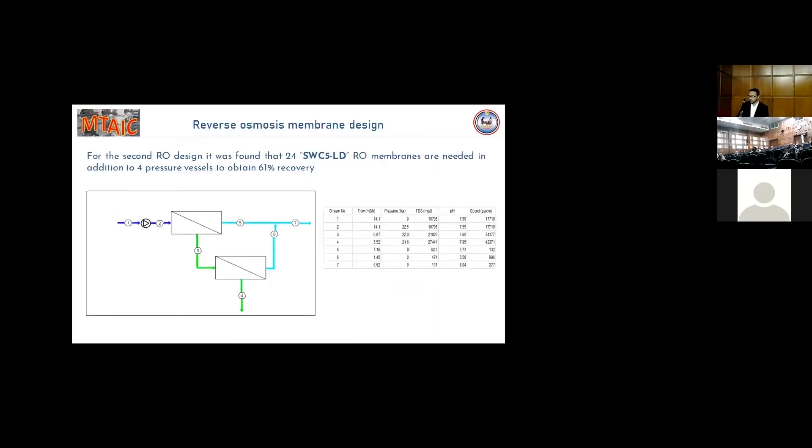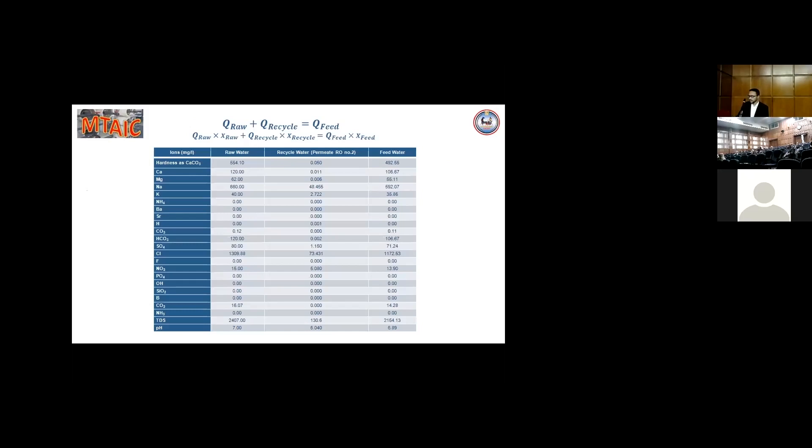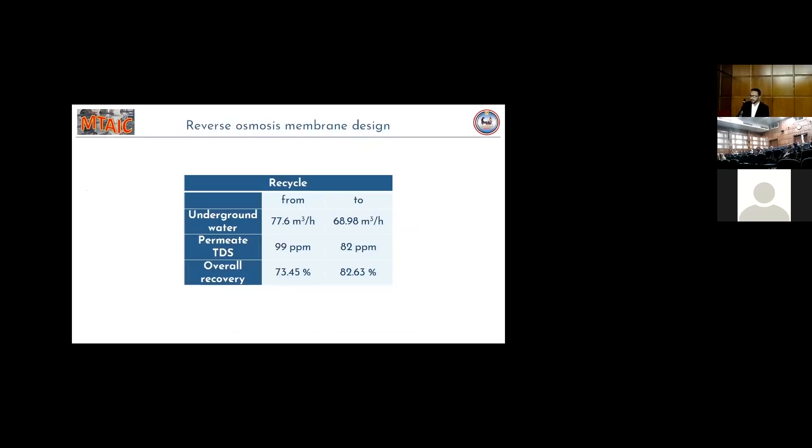The second RO is found that it needs 24 membrane elements of SWC5-LD to obtain the maximum recovery of 61%. The permeate from the second RO, which will be recycled in the mixer with the raw water and the mass balance is applied to get the mixed stream. The recycle is done to decrease the underground water needed, decrease the feed TDS and increase the overall recovery.